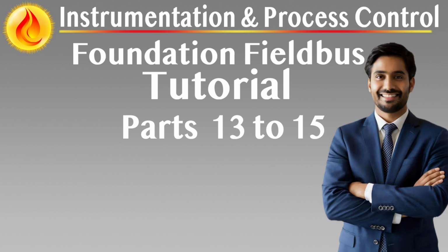Once physical installation is complete, pre-commissioning checks must be performed. These include continuity tests on all cable segments and spurs. Resistance checks across terminators should read approximately 50 ohms. Isolation testing between conductor and shield ground. Visual inspection of terminations, labeling, and cabinet layout. Verification of device polarity, integrity of cable dressings, and proper enclosure sealing.